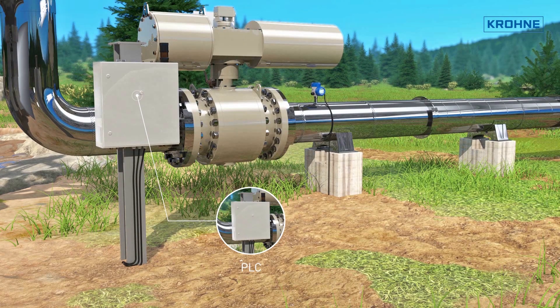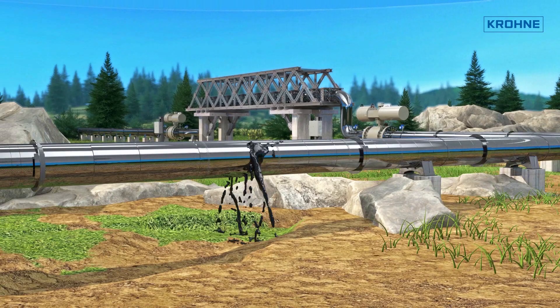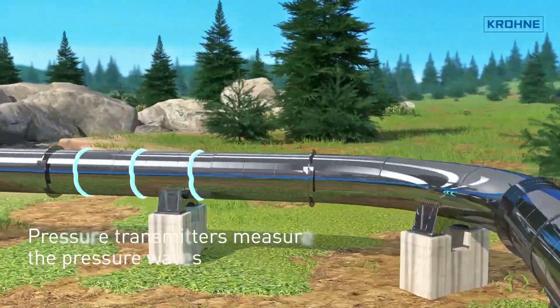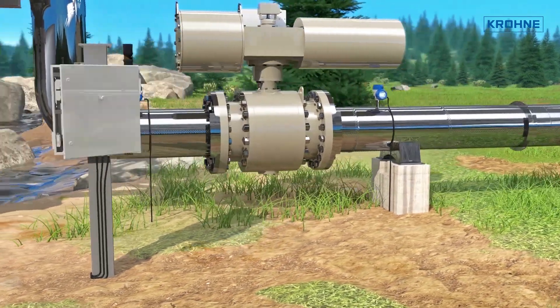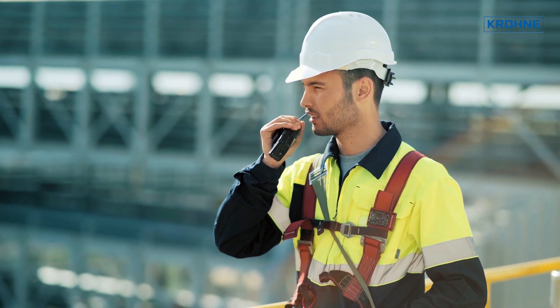Pipe Patrol Line Break Detection is a dedicated system to identify pipeline ruptures instantly. It consists of a local PLC with rupture pattern recognition, an ESD valve, plus pressure transmitters to act as the pipeline rupture detection sensors. The system immediately recognizes the rupture pattern and raises an alarm. The automatic emergency shutdown procedure starts right after — the valve closes and the flow of the medium is stopped.